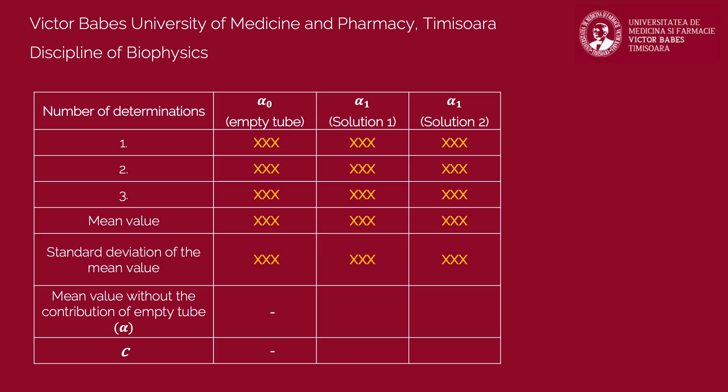To correct the calibration of the polarimeter, subtract the rotation with the empty tube from the values obtained with the two solutions inside. The results represent the net contribution of fructose in rotating light's polarization plane. Using these two values, calculate the concentration of the two solutions using the given formula.